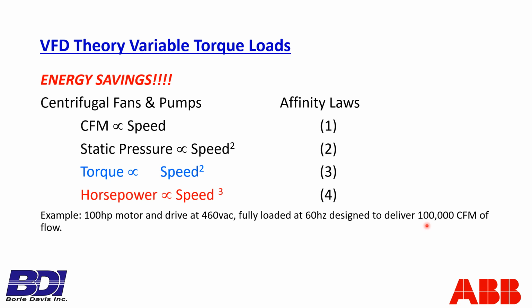So let's look at 80,000 CFM. That would be 80% speed. 0.8 times 60 is 48 hertz. So at 80% speed, 48 hertz, the power required to deliver 80,000 CFM is equal to 0.8 times 0.8, that's 0.64, times 0.8 is 0.5. 50% energy to deliver 80% flow, 80,000 CFM. You have a 50 horse load at 80% speed on a 100 horsepower system design.